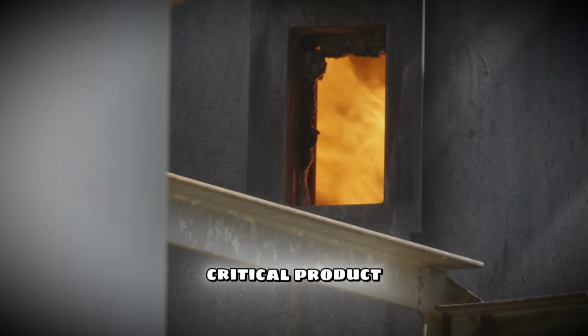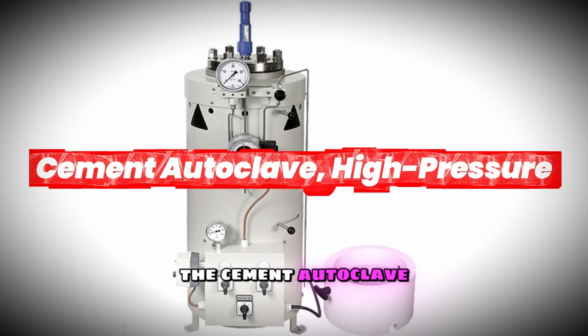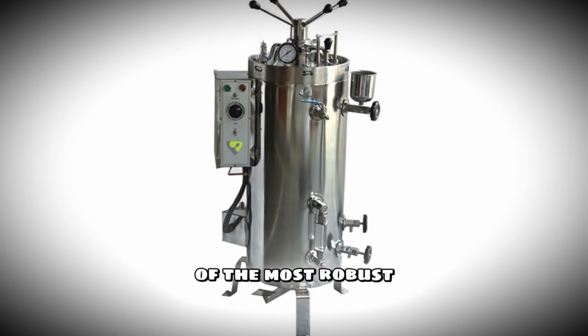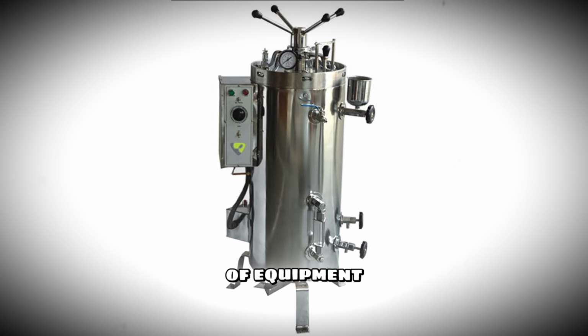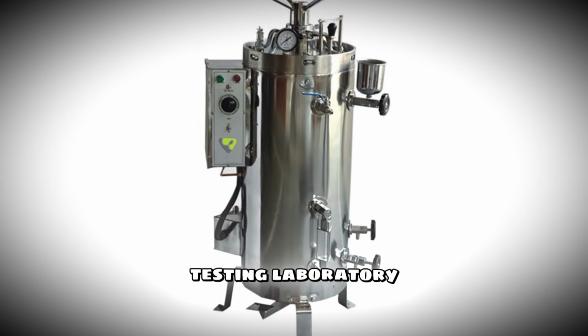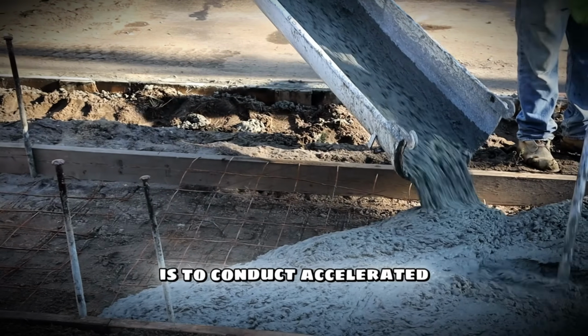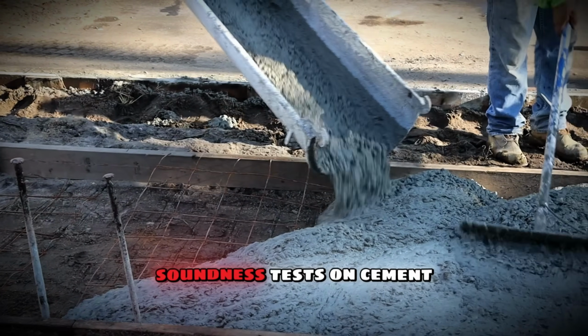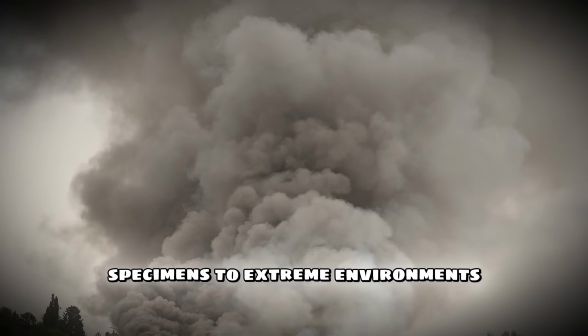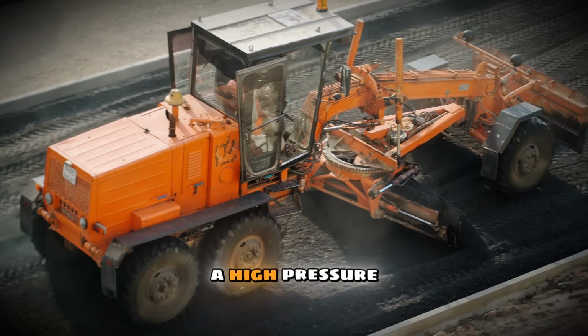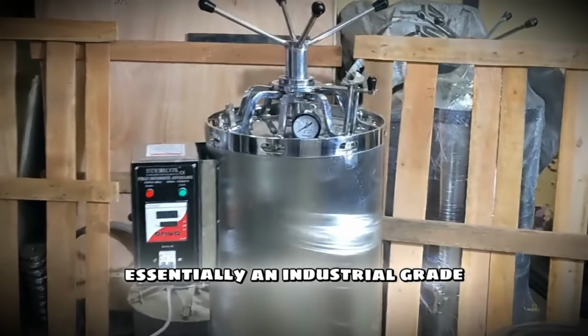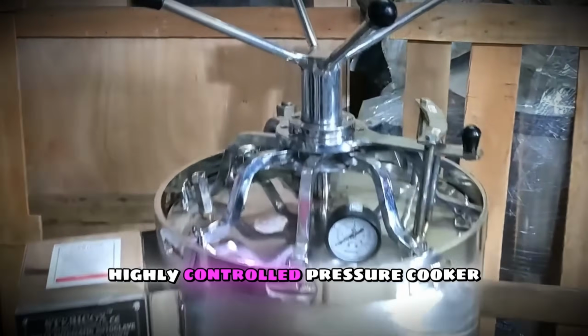Enter our second critical product, the cement autoclave, high pressure. This is one of the most robust and impressive pieces of equipment you will find in a materials testing laboratory. Its primary usage is to conduct accelerated soundness tests on cement by subjecting cured specimens to extreme environments. A high-pressure cement autoclave is essentially an industrial-grade, highly controlled pressure cooker.